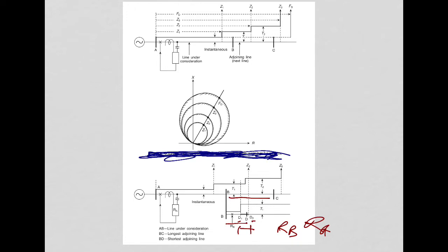One more, again we can discuss that. Let us suppose that there is a fault in the region between D1 and D2. Here, as we have seen, there is the fault in the region between D1 and D2. Now, if we have set the reach for the longest line, in that very case, what happens?